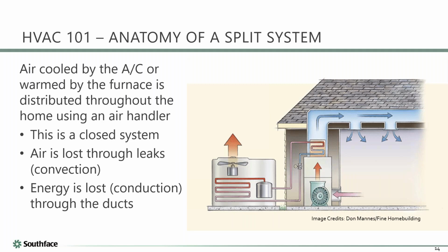This is supposed to be a metering device. It's usually, of course, inside your coil here. And that liquid meters from a high pressure liquid to a low pressure liquid. It boils and it comes out cold. So it's low pressure and it's cold. And then, of course, you're moving house air across it, and it's causing that refrigerant to boil out again, and the vapor is now leaving.